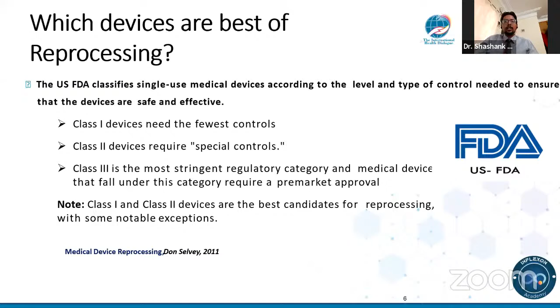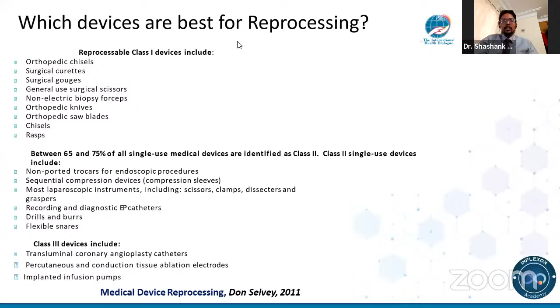Now, if you look at processing, as we said, most of the single-use classes of devices which can be reused are the ones which fall into class 1 and 2. That's what most of the current regulation of the US FDA talks about. But class 3 devices, which are single-use devices like your catheters, your guide wires, and other things, should preferably not be reused. But as we know here in India, a lot of these devices are being reused.